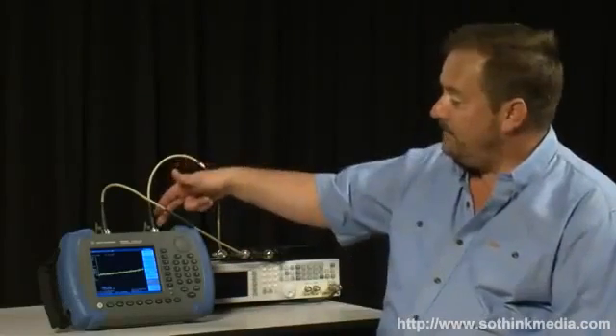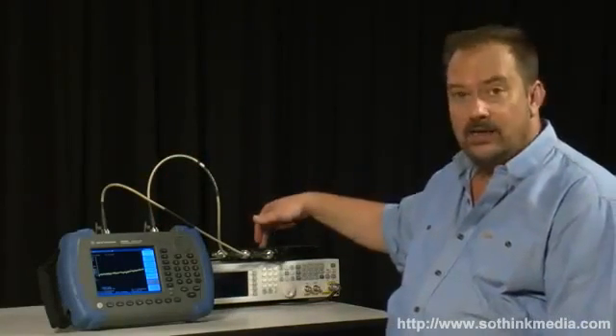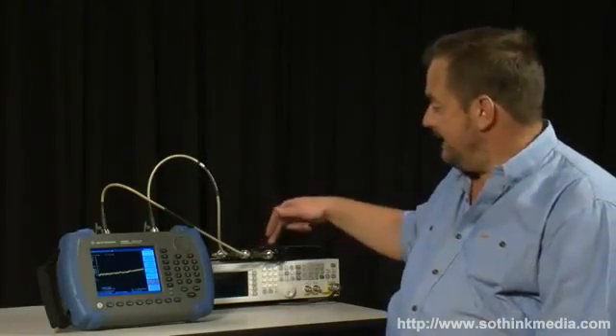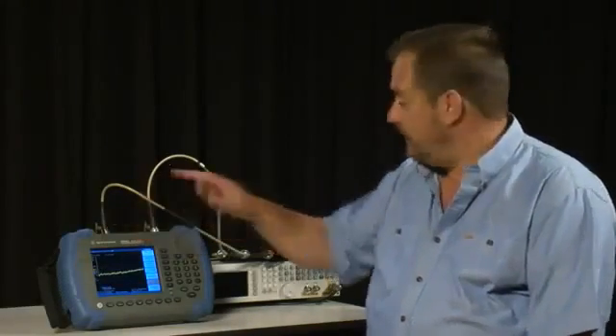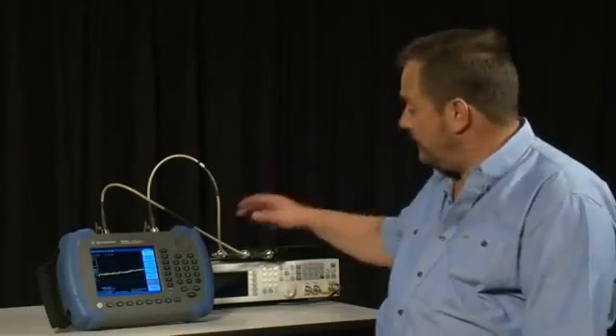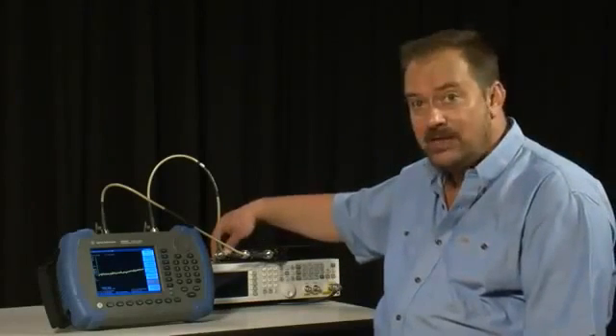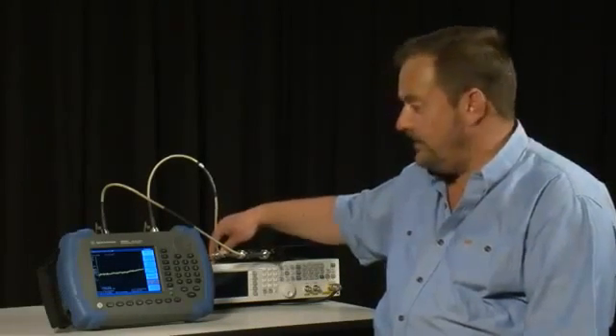So I have connected the tracking generator output to one of the inputs on the filter, and the output from the filter to the input of the spectrum analyzer. Now, don't forget, if you are measuring a three-port device such as this, remember to terminate any unused ports with a 50 ohm load.